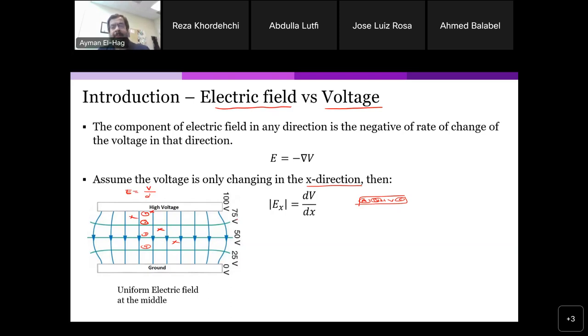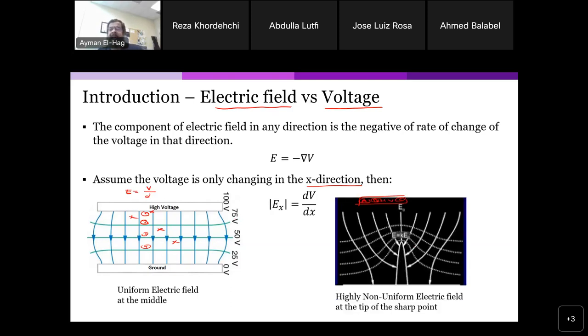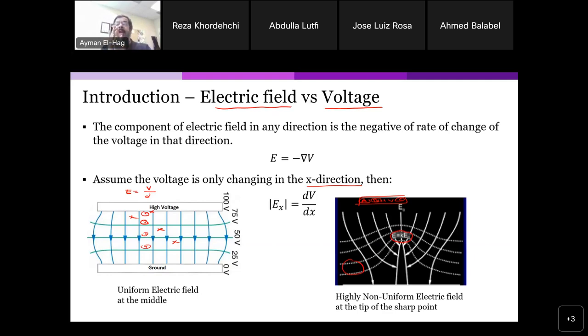In most power system components, the electric field is not uniform. Here is an example around a sharp point. The dotted lines are equipotential lines — near the tip they are very close together, and they spread apart as you move away. This means the electric field is much higher at the tip than further away. When the voltage changes over a very short distance, we have high electrical stress.